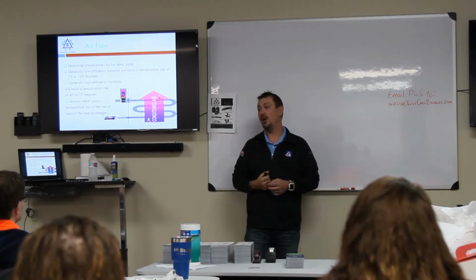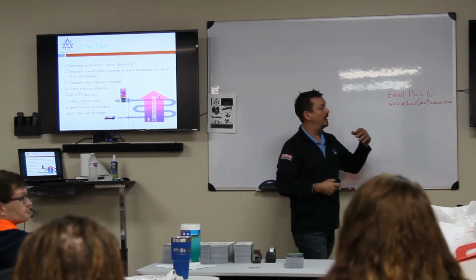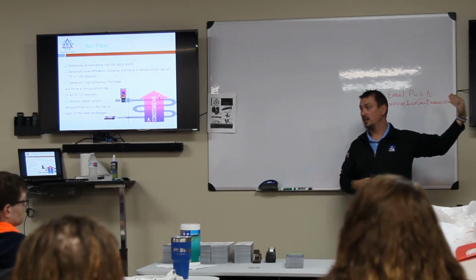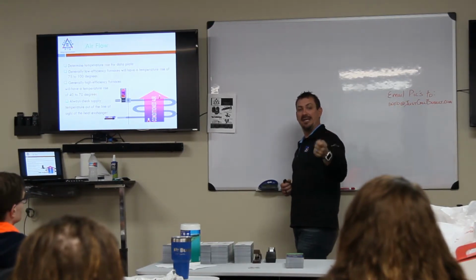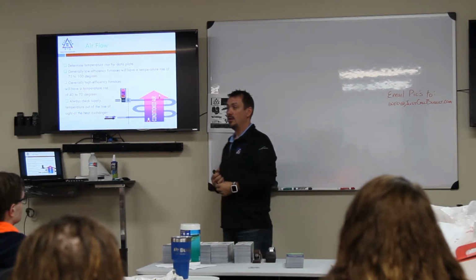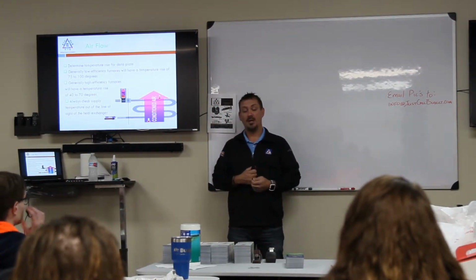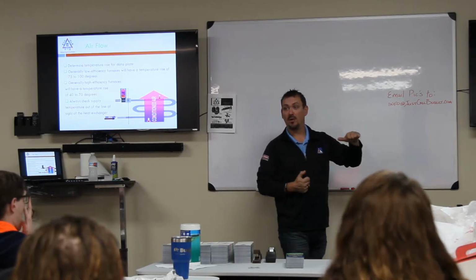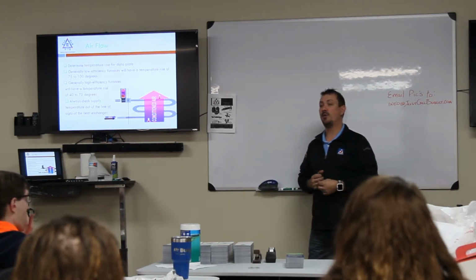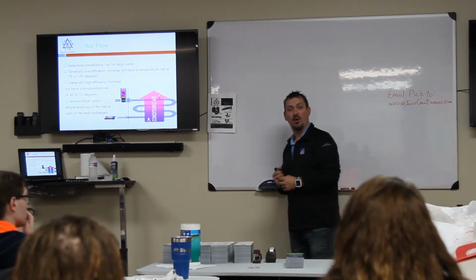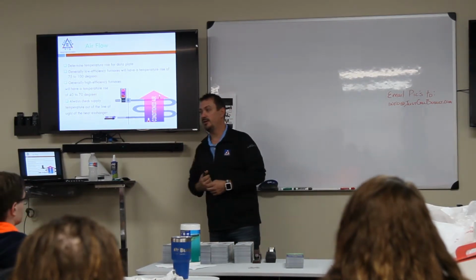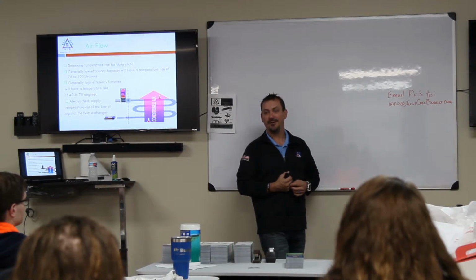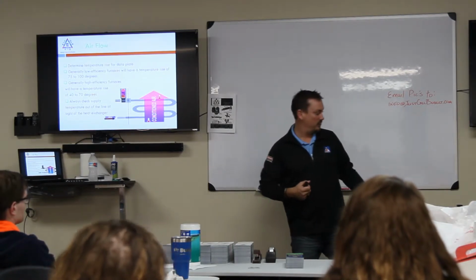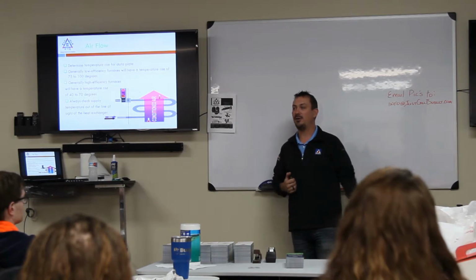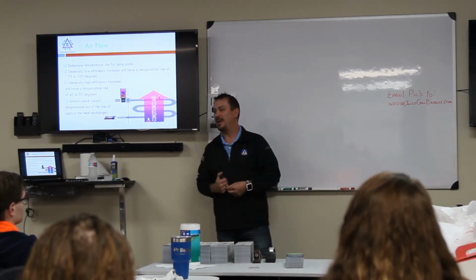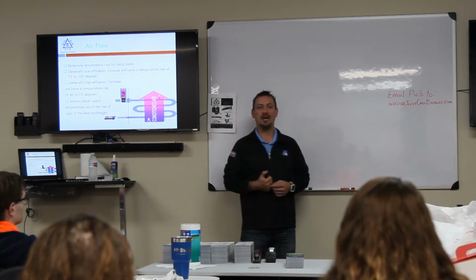Now, if I'm running a little bit too heavy, if I'm running more towards the 70-degree mark, I'm going to want to speed my blower up. I'm going to want to increase my blower speed to get it more towards the middle of that range. The reason for that is, what happens when they give us a call to come out and do a clean and check? What do they do just before we get there? Change their filter, right? They change their filter just before we get there, and then you look over in the corner and you'll see this thing that looks like a cat or a dog sitting over there, and it's the filter, because it's been matted and in there since 6 months before you got there.